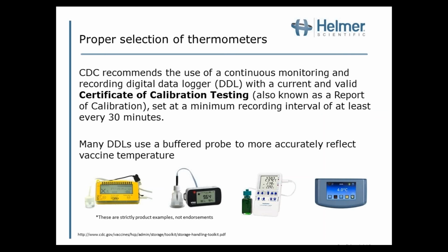So to start off with, I wanted to spend a little bit of time talking briefly about the proper selection of thermometers. Like I mentioned, it is an often overlooked topic. The CDC recommends the use of a continuous monitoring thermometer with a recording digital data logger with a current and valid certificate of calibration testing. So what that means is the thermometer is recording, as I put here, every 30 minutes at a minimum, taking a temperature. And each time it takes a temperature, it downloads it into a log that, depending on the thermometer, you can access. You see the thermometer on the left, you can access it through a USB port and download those reports into your computer. So in the case of an excursion, you can see exactly how long that unit was exposed to that excursion.